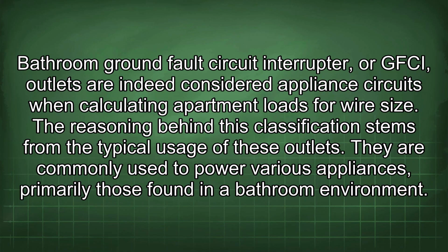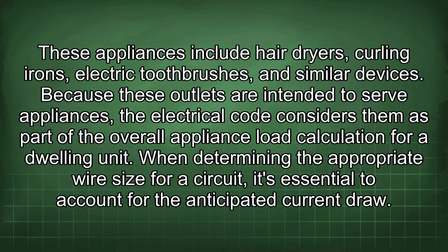Bathroom ground fault circuit interrupter, or GFCI, outlets are indeed considered appliance circuits when calculating apartment loads for wire size. The reasoning behind this classification stems from the typical usage of these outlets. They are commonly used to power various appliances, primarily those found in a bathroom environment. These appliances include hairdryers, curling irons, electric toothbrushes, and similar devices. Because these outlets are intended to serve appliances, the electrical code considers them as part of the overall appliance load calculation for a dwelling unit.